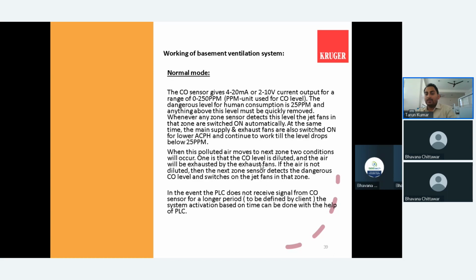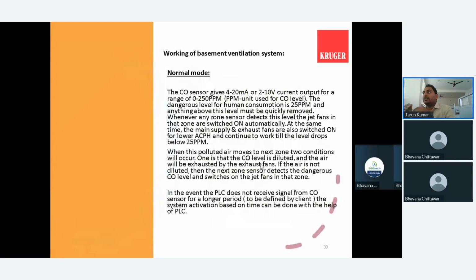Whenever your CO ppm level is below 25, nearby to 25 ppm, the fan will start running at low speed. The CO sensor will give the signal to the PLC panel, and the PLC panel will give the signal to the nearest jet fan, which will evacuate the carbon gases nearby, whatever hazardous gases are there. They will be pushed towards the next jet fan, as well as towards the nearest exhaust fan. So that is basically the normal mode.